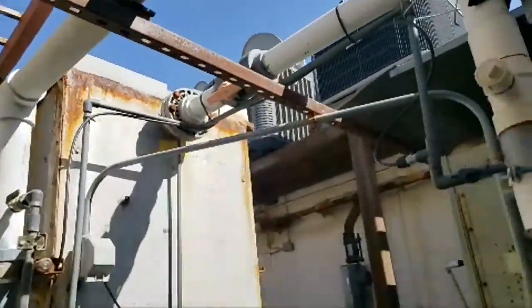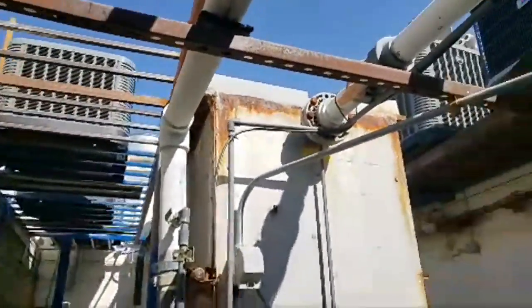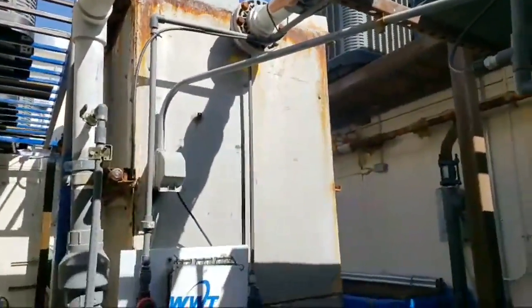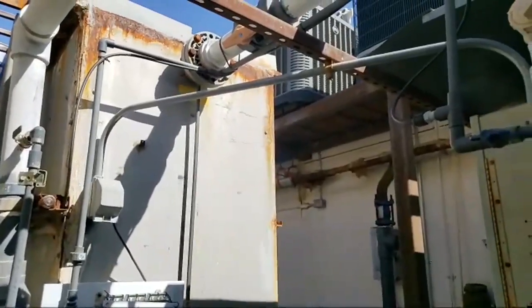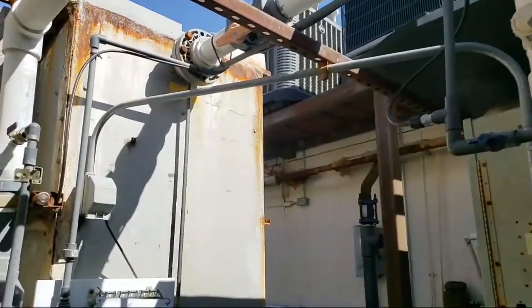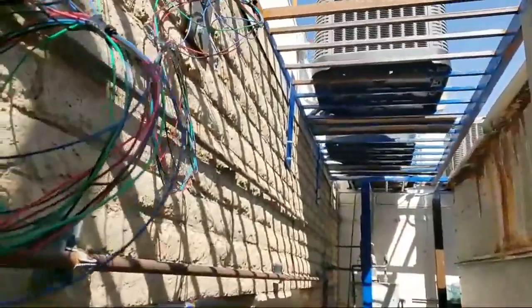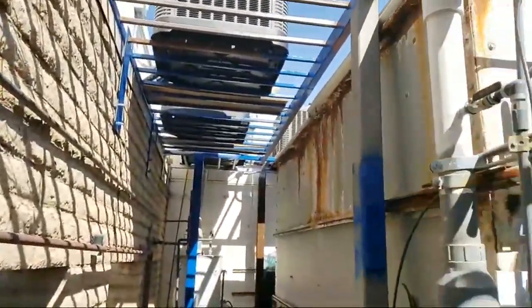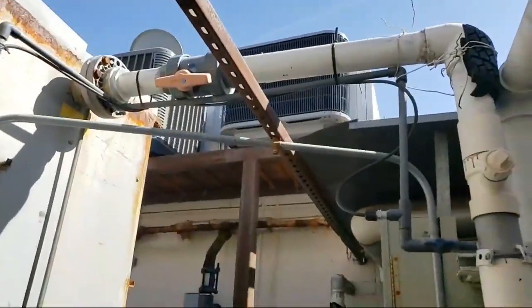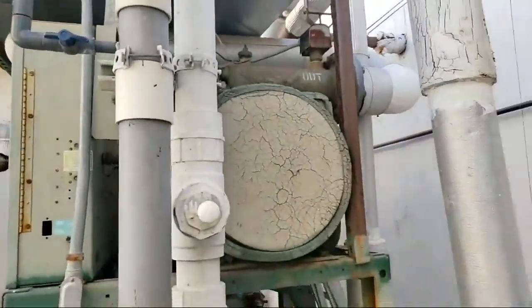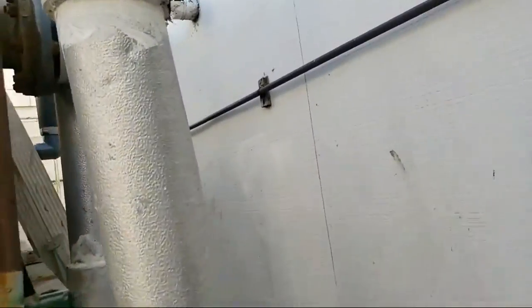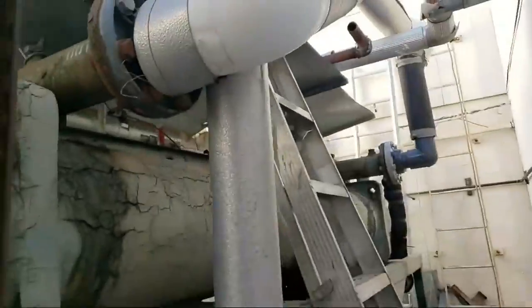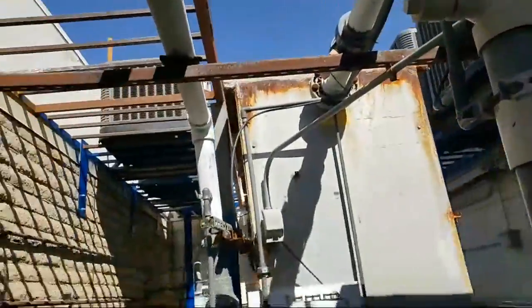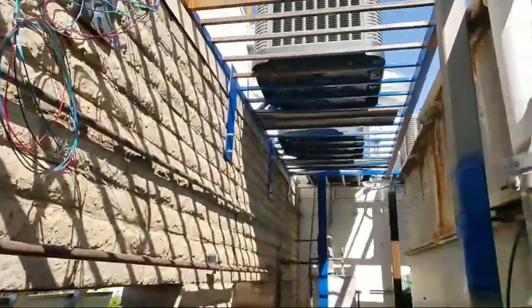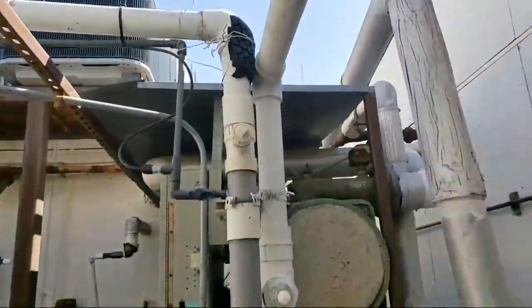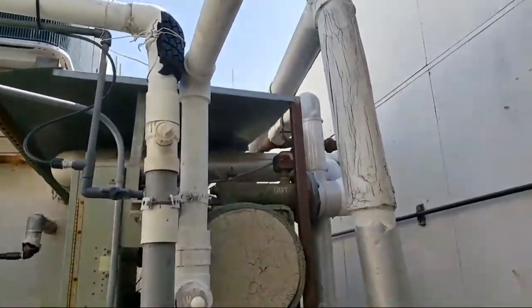I was just telling them today we should continue that steel across the top when they remove the tower, because by code you should have a 30-inch platform all the way around, and technically the electrical access compartment should be 30 inches from any obstruction. He kind of was shocked. I said, yeah, this is Phoenix, where nobody enforces codes anymore, so we're correct, but if you were in another state where they did enforce codes, you wouldn't get away with a lot of the stuff you're seeing here and having to deal with.